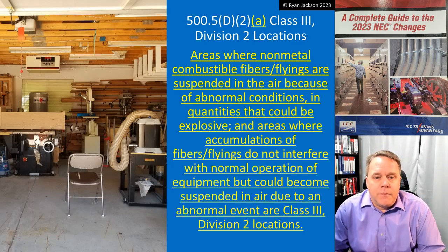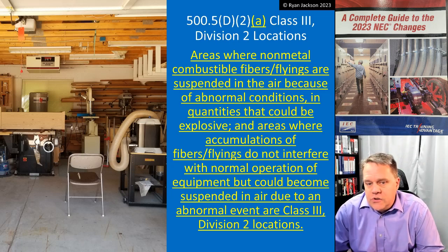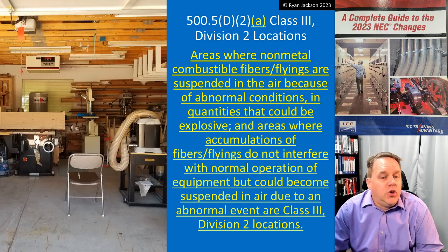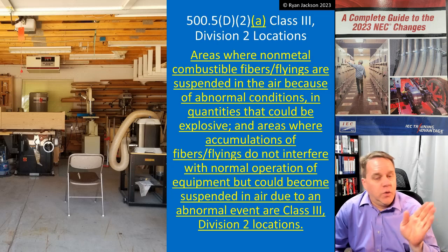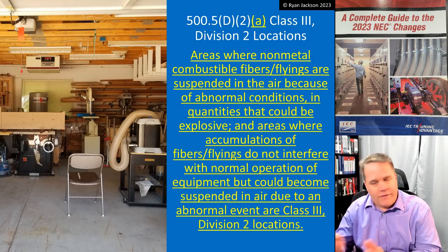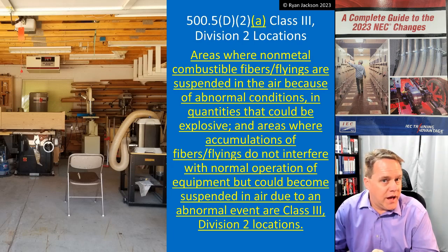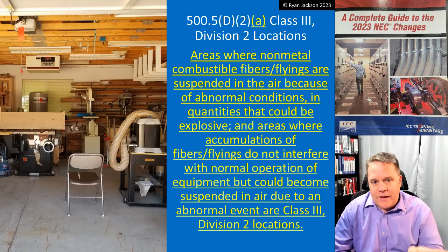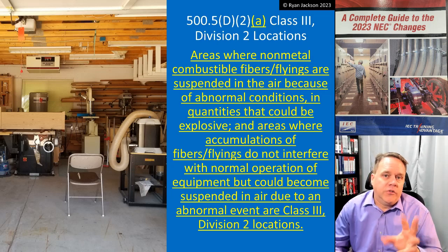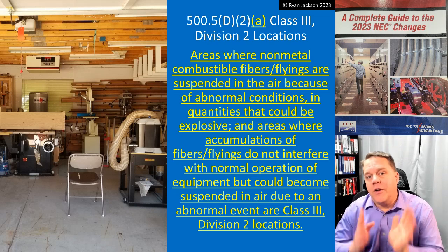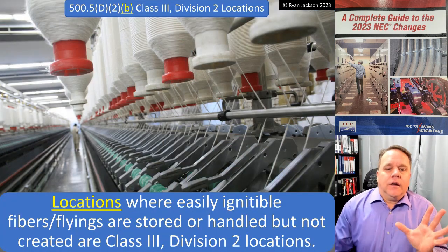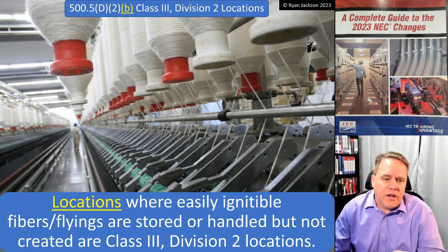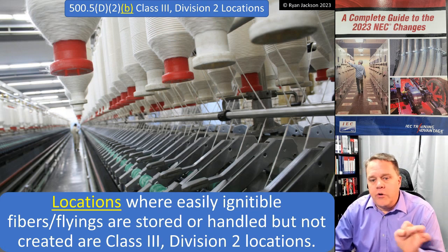Class 3 Division 2 locations are areas where non-metal combustible fibers or flyings are suspended in the air due to abnormal conditions in quantities that could be explosive, and areas where accumulations of fibers and flyings don't interfere with normal equipment operation but could be suspended in the air due to an abnormal event. For ignitable fibers and flyings, Class 3 Division 2 locations are where they are stored or handled but not created.